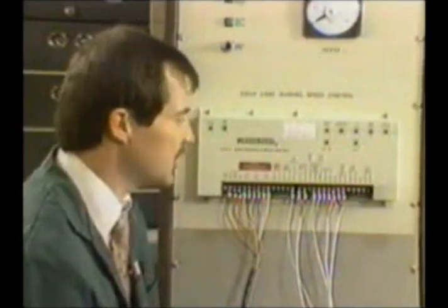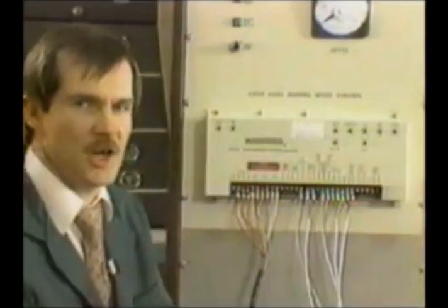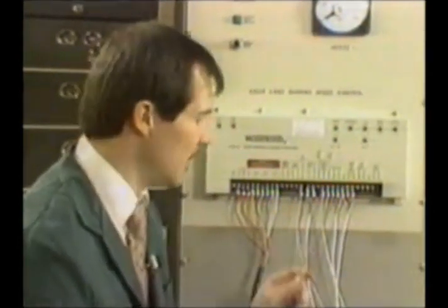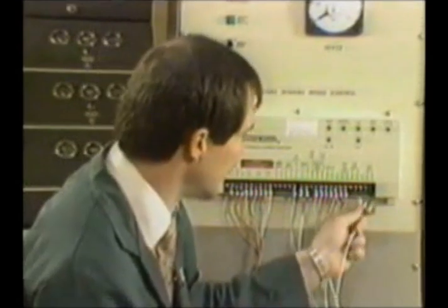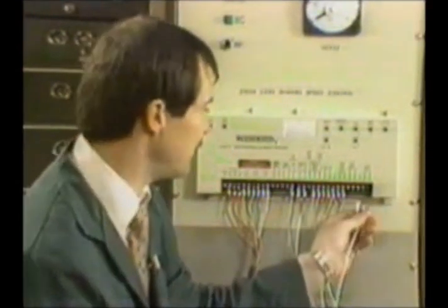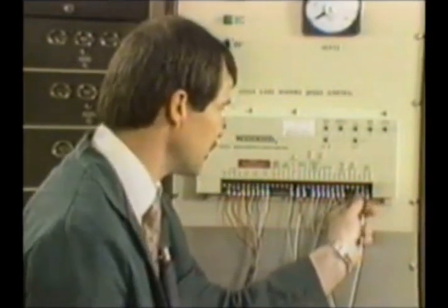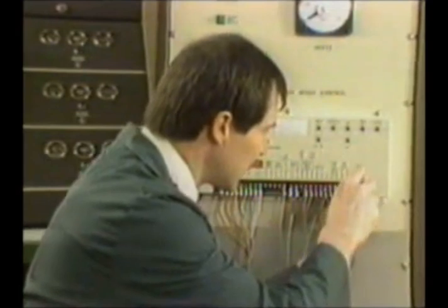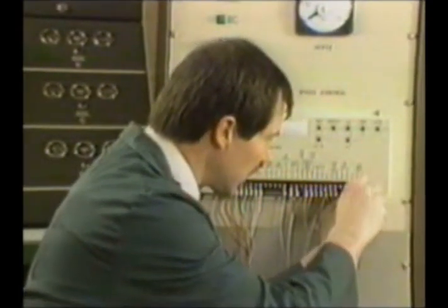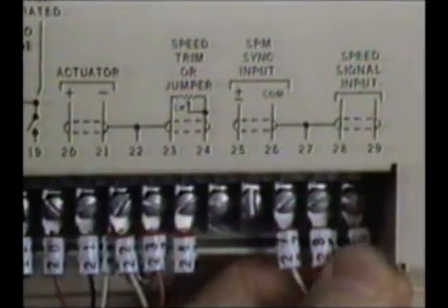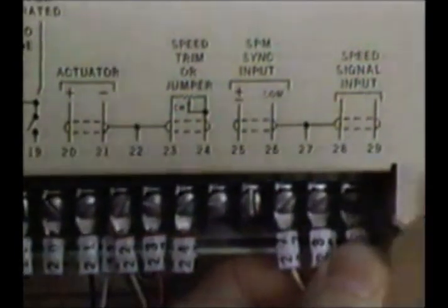Terminals 25 and 26 are your SPM synchronizer input. We are not using an SPM synchronizer today, so nothing will be hooked to that input. But if you do, that's also a shielded pair with a terminal being terminated on terminal 27. Then our last input will be our speed signal input. For our speed signal today on the Caterpillar, we're using a magnetic pickup. I have that coming out here. And 27 is also the shield for that shielded pair to be terminated at the 2301A. So now we have all of our wires connected up to the control.